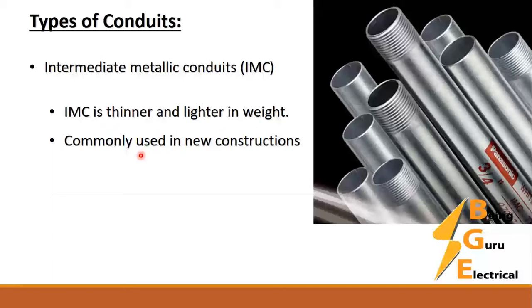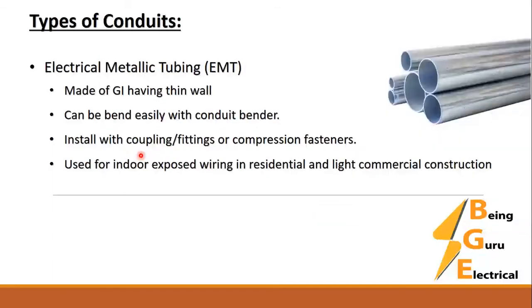The third type is Electrical Metallic Tubing, or EMT. It is made of galvanized steel with thin walls, so it can be bent easily with a conduit bender. It does not have threads and is installed with couplings, fittings, or compression fasteners. It is used for indoor exposed wiring in residential and light commercial construction buildings.